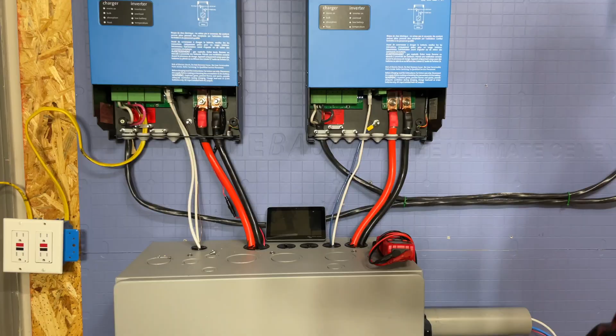So the computer and stuff you have connected to this type of unit won't have any issues with that. Let's talk about the connections to the units real quick. This is a RJ45 Ethernet cable, standard cable that comes out of this unit, and it connects to VE bus on this unit. There are 2 ports, and it doesn't really matter which one you connect it to, because it's pretty much like an Ethernet type switch. So it doesn't matter whether you connect it on the first port or the second port for VE bus, as long as they're connected together.